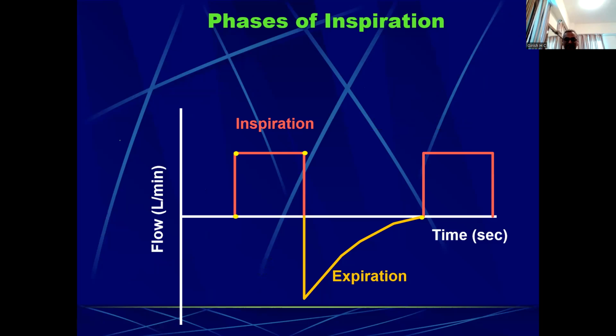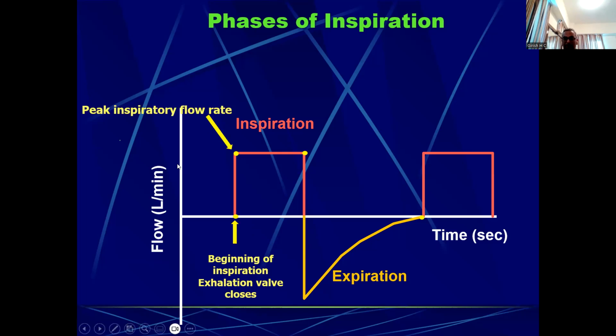So basically, we'll talk about these three phases, because we forget about exhalation, since exhalation is passive. Now we will start with the beginning of inspiration. That is when the exhalation valve closes. Then a gush of air comes into the patient. So this is one important phase. The second one is when peak flow is reached in order to achieve a certain tidal volume or certain pressure. And then the exhalation valve opens so that the patient can exhale. So these are three important phases which determine what type of mode we are using and what type of breaths happen.